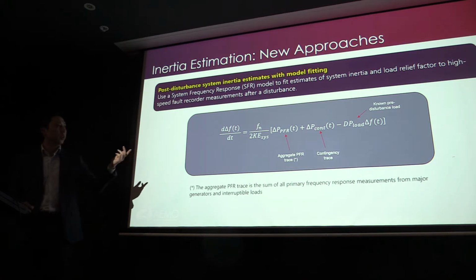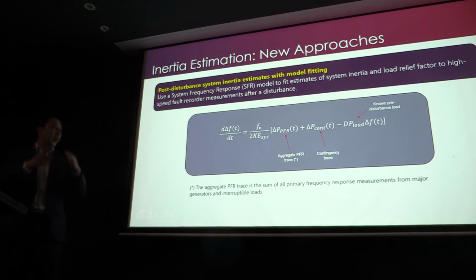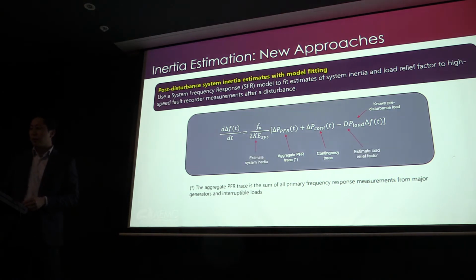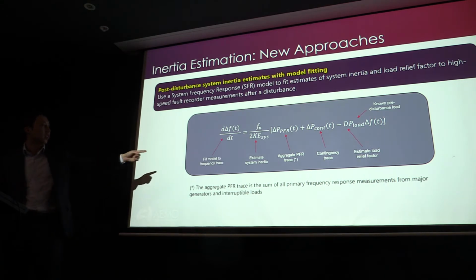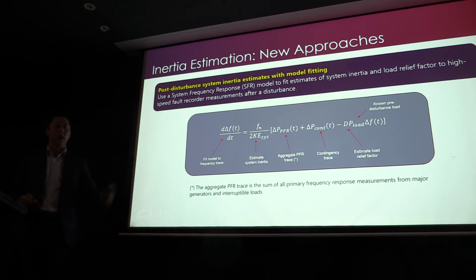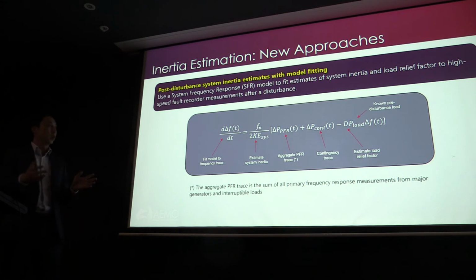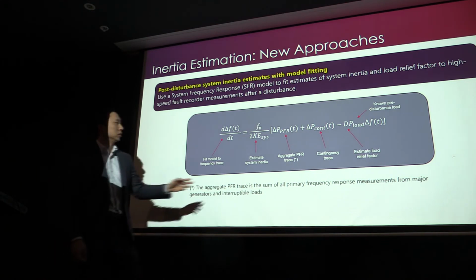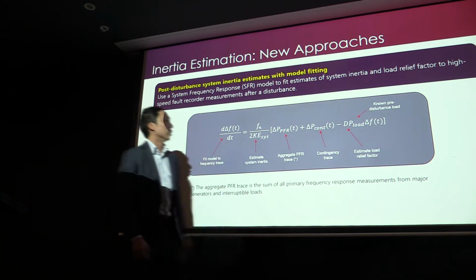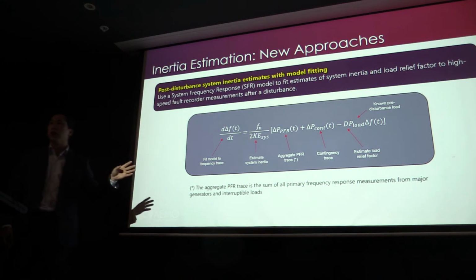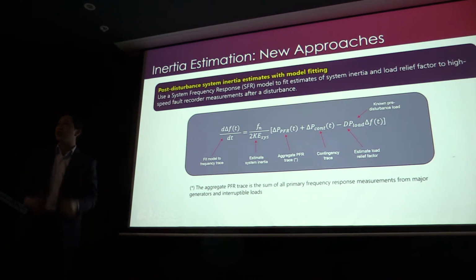We also know what the aggregate PFR is, so we're basically adding up all of the primary frequency response traces from all the generators that we know provide PFR. And what we're trying to estimate is the system inertia and the load relief factor, and we're fitting all that to a known frequency trace. So basically the idea is we're trying to use more of the swing equation, because the linearized swing equation only uses this bit and then this bit at t equals 0. So we're trying to use more information that we've got from the high speed data.